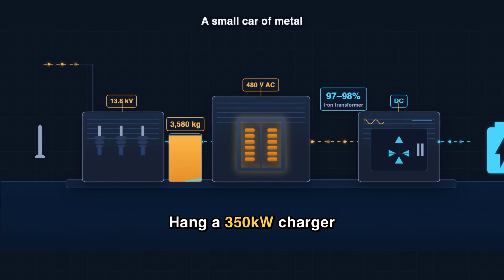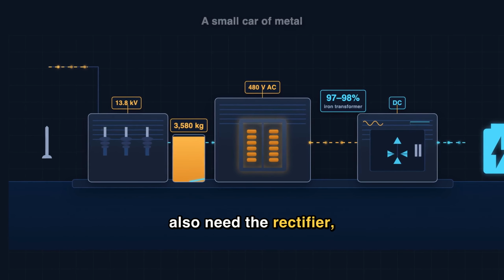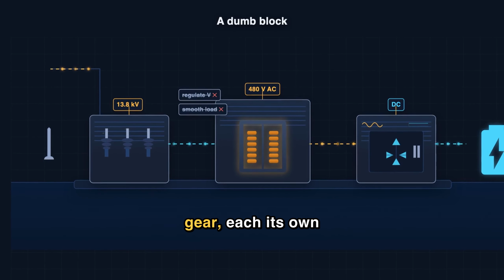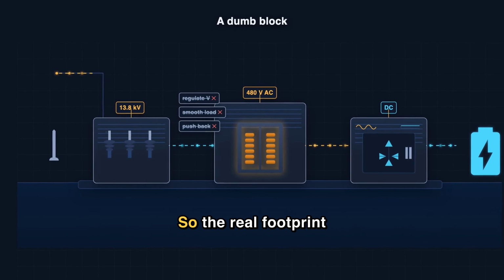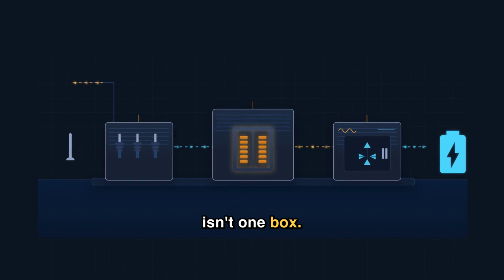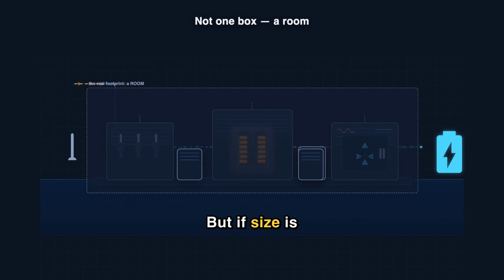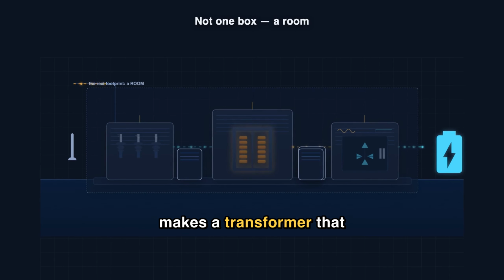Hang a 350 kilowatt charger off it, and you also need the rectifier, the filters, the protection gear, each its own cabinet on the pad. So the real footprint is not one box, it is a room. But if size is the enemy, what actually makes a transformer that big?